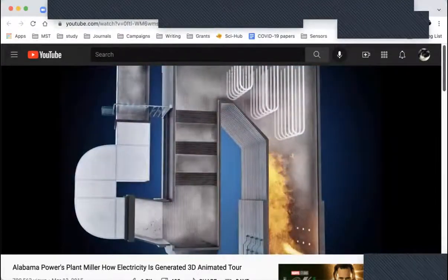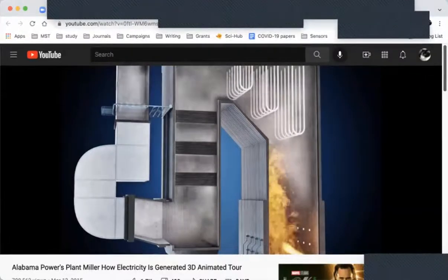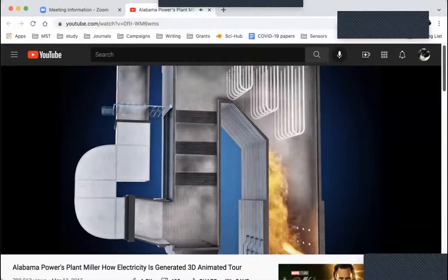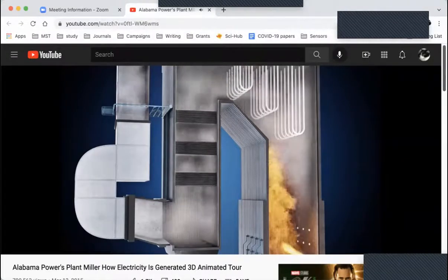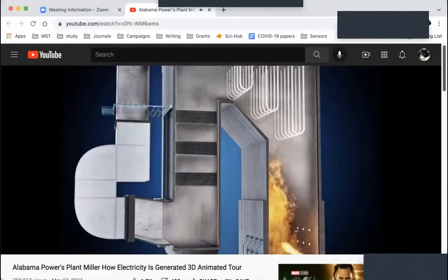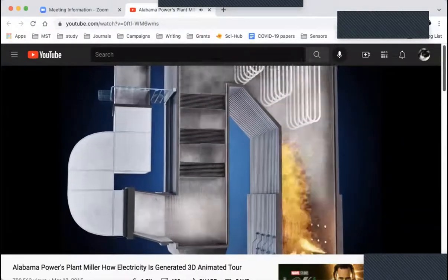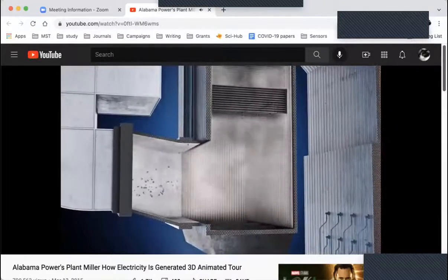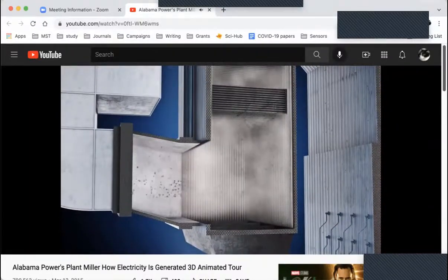While the heavier particles of ash fall to the bottom of the boiler, the hot flue gas containing finer particles of fly ash naturally flows up to the top of the boiler and around, down, and out through the backpass section. The last section of the boiler is the economizer. Because of the shape and the flue gas flow path, some of the fly ash falls out here into hoppers.